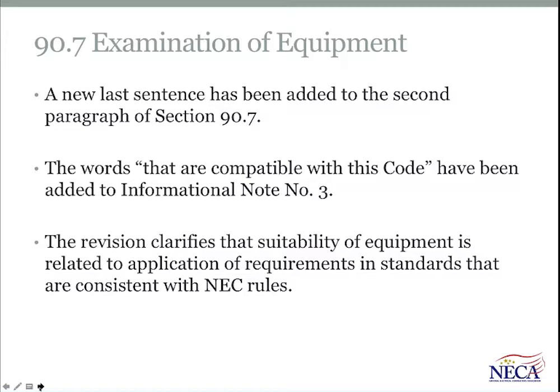There are many standards in the North American safety system and beyond, worldwide standards. Some are totally compatible with the NEC and others are not. And this change in 90.7 and associated informational note provides the needed clarity that the conductors and equipment and the standards they're built to must be compatible with the installation requirements of the NEC.